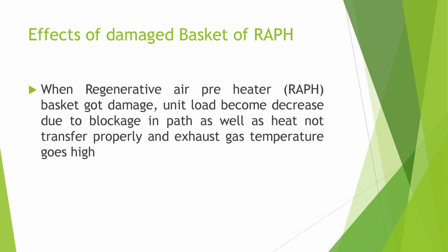Effects of damaged basket of RAPH. When the regenerative air preheater basket got damaged, unit load decreased due to blockage in the path, as well as heat not transferring properly, and exhaust gas temperature goes high.